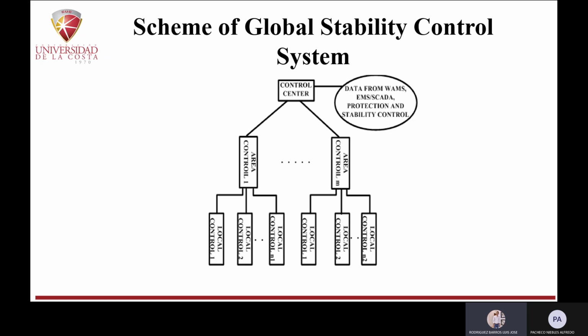The block diagram of the global stability control system is shown in this figure. The control center receives global system data from WAMS, EMS, and SCADA, protection and stability control, to analyze system stability and compute the control strategy, and then sends control commands to the control stations. When the operation of the power system is in a normal condition, with the variety of operation modes, network topologies, and system parameters, the transmission limit can be updated in the control center and then sent to local control devices in real time. Therefore, the power system can operate in a wide region without losing security and avoid wasting the resources of electrical power.